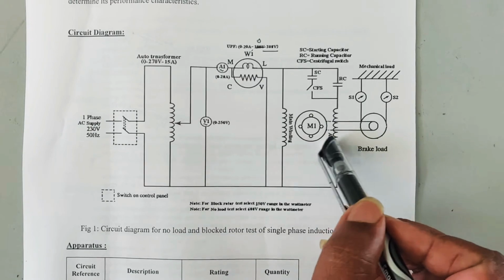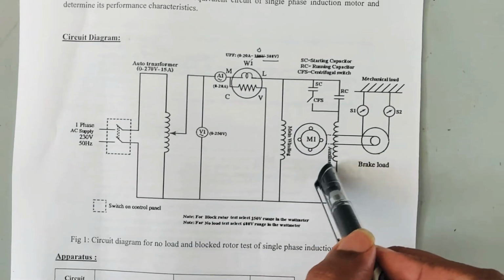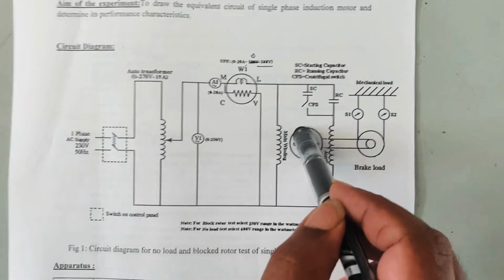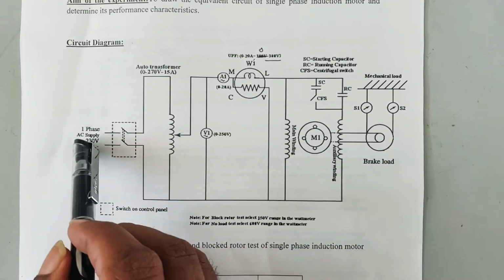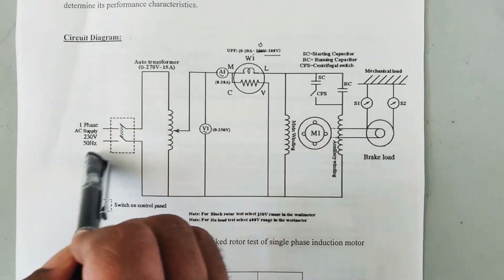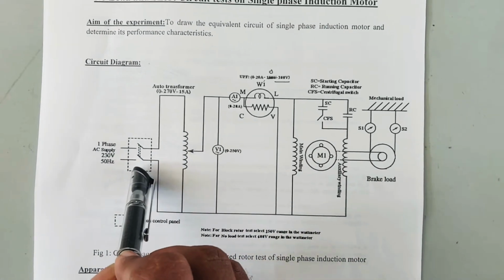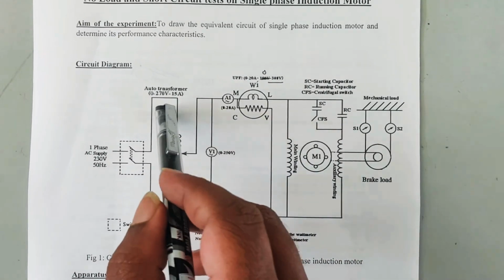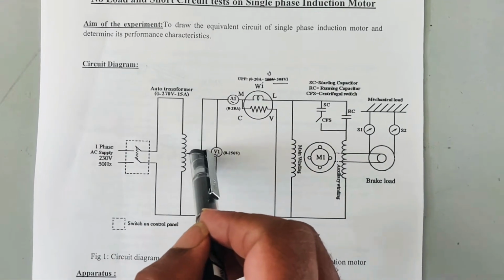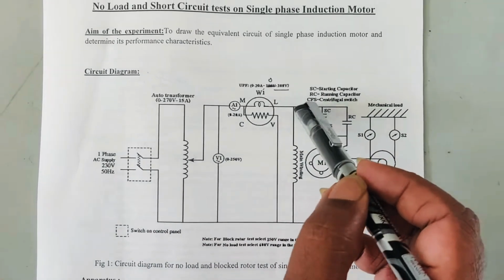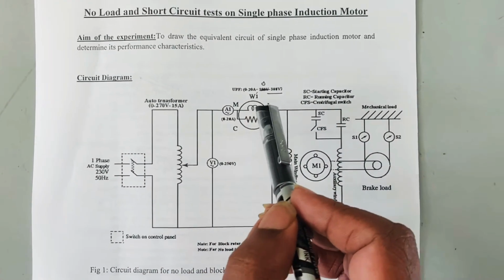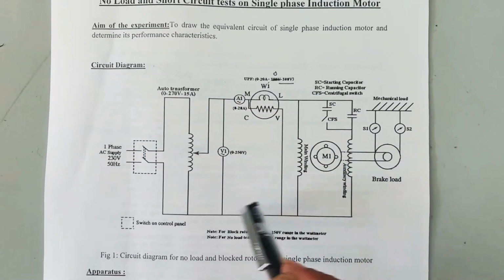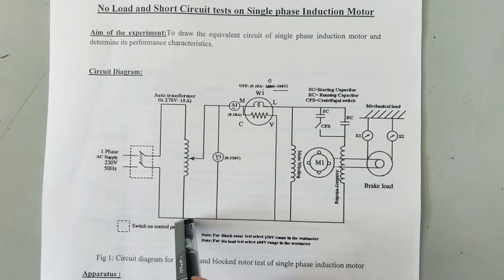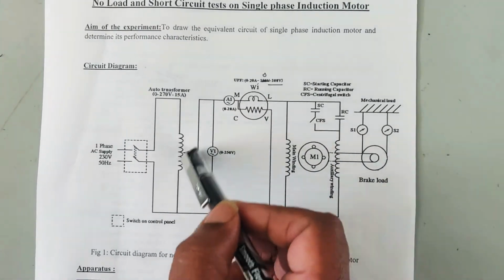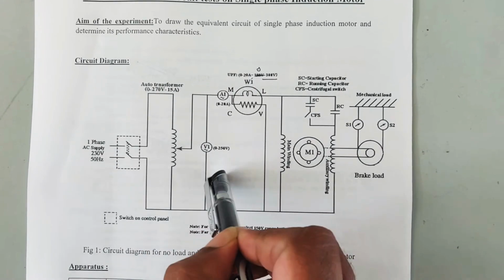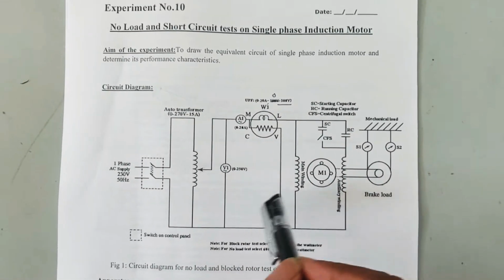And in the construction it basically has two windings, the main winding and the auxiliary winding. This part is the induction motor, and the single phase AC supply is given from the main panel, and then it will be given to the MCB. The MCB output will be given to the auto transformer, a single phase auto transformer. The auto transformer phase point is connected to the main winding phase point through an ammeter and then a wattmeter, and the neutral point of the main winding is connected to the neutral point of the auto transformer.